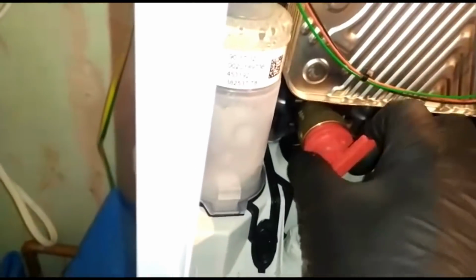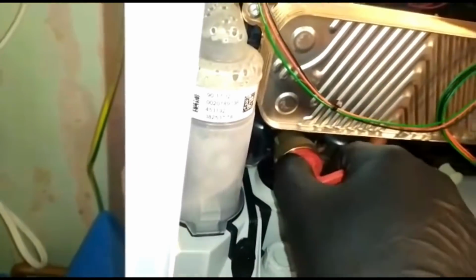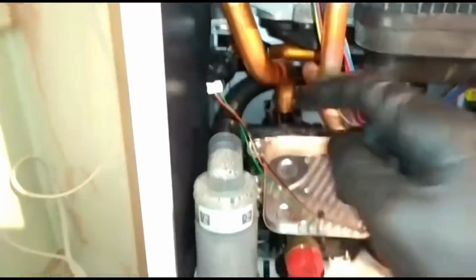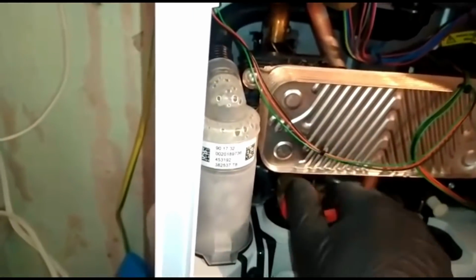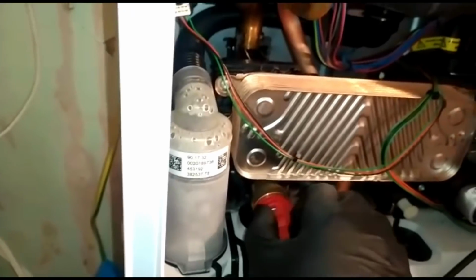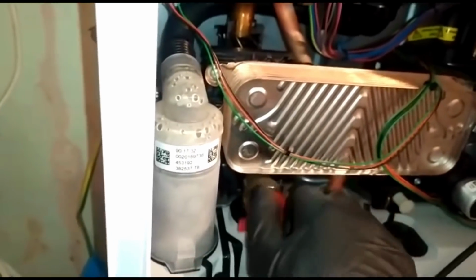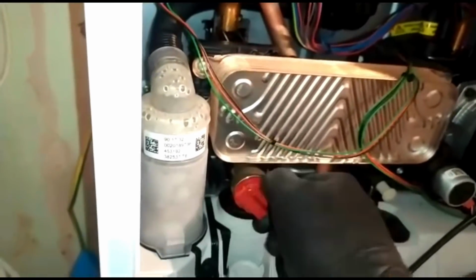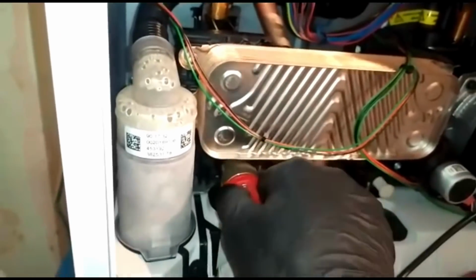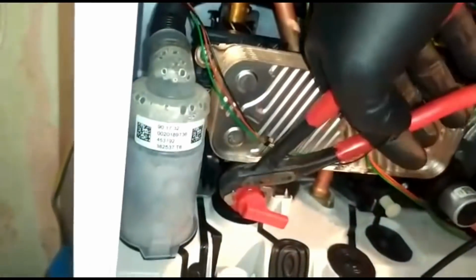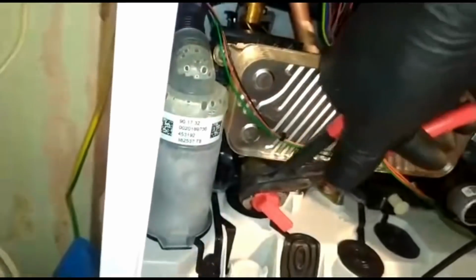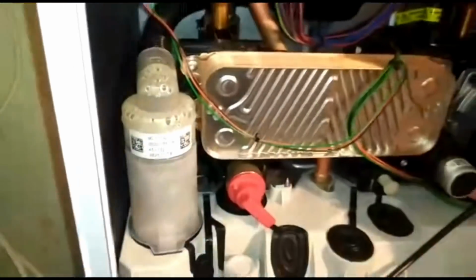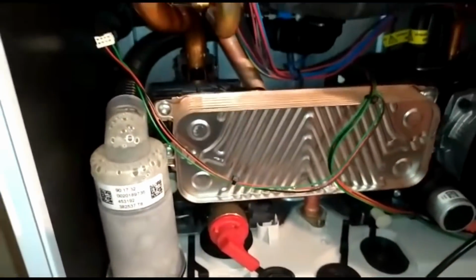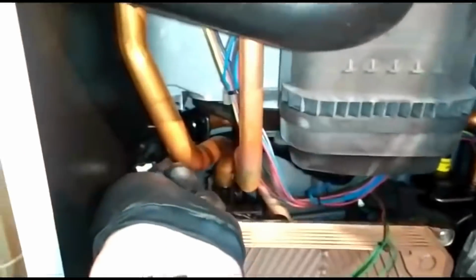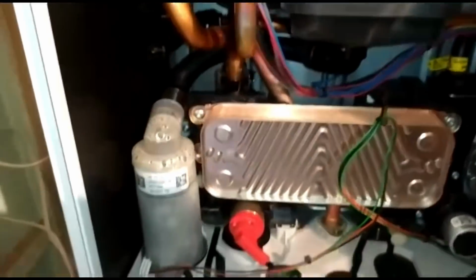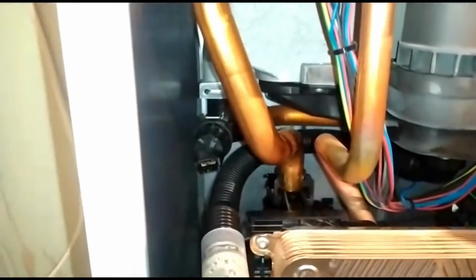But the importance of carrying out the servicing. Now, I carry the pressure sensors for the Glowworm and Vaillant in stock because I fit a lot of these products. So even though this boiler's got a 10-year warranty and it's only 4 years old, I think, I'm going to change over the pressure sensor because I don't want this to break down or read too high a pressure when in fact the heat exchanger is empty of water, and then the customer gets a rather big breakdown and a main heat exchanger change or something like that.